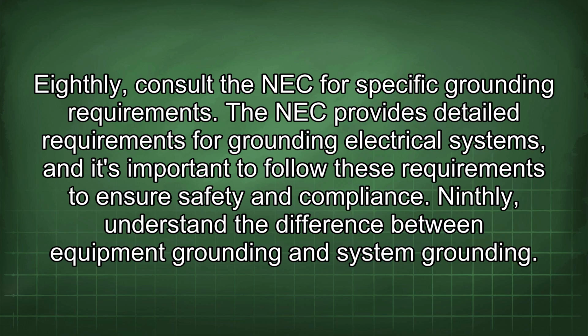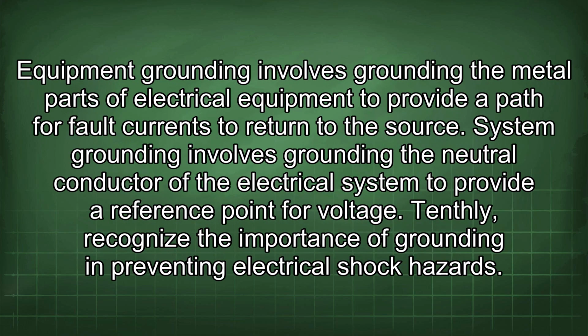compliance. Ninthly, understand the difference between equipment grounding and system grounding. Equipment grounding involves grounding the metal parts of electrical equipment to provide a path for fault currents to return to the source. System grounding involves grounding the neutral conductor of the electrical system to provide a reference point for voltage.